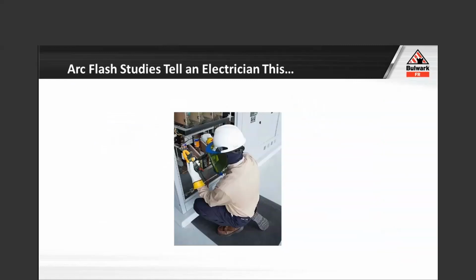The other piece of that puzzle when it comes to PPE and what the arc flash studies tell an electrician is how big a bomb you're actually sitting in front of, because it'd be very, very good information to know if the incident energy is 5 calories or 25 calories. Completely different exposures, completely different sets of PPE, simplifying, one's Cat 2, one's Cat 3. One's going to be very, very similar to the moon suit that we all commonly see in the workplace, and the other one is a shirt, pant, or coverall. I would like to know that.